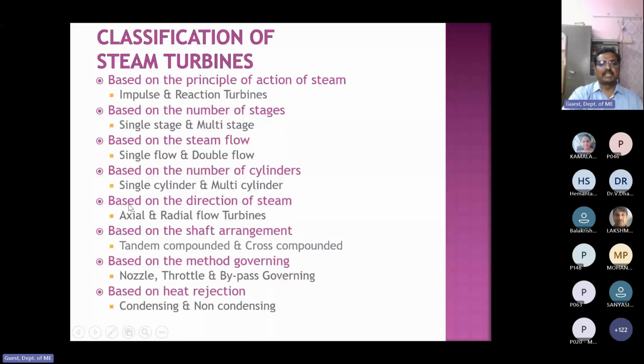Another classification is based on the direction of steam flow. It is an axial flow or radial flow. Axial flow means the steam flows along the axis of the shaft; that is called an axial flow turbine. If the steam flows across, that means normal to the shaft, it is called radial flow.